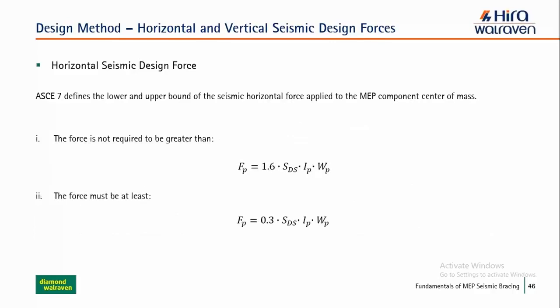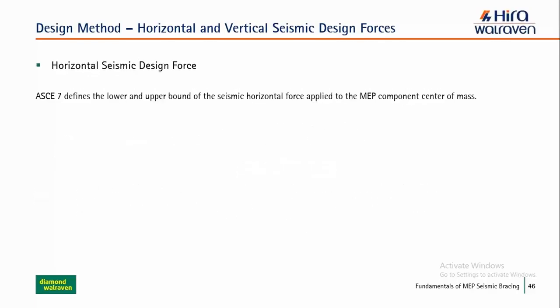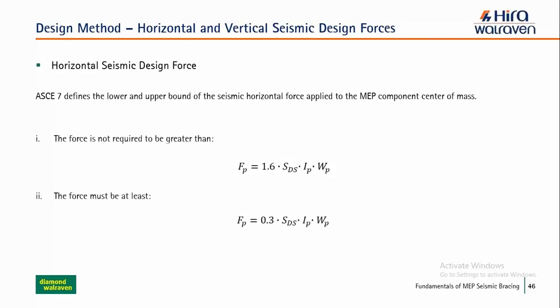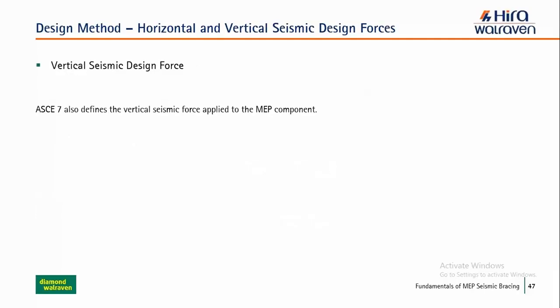Now we have upper and lower limits to counter check our values. This force is not to be greater than 1.6 times this equation, and this force must be at least 0.3 times this equation, the second one. If our Fp value comes out lesser than the force 0.3 SDS Ip Wp, in that case we need to consider the force coming from this equation. That is the reason the force must be at least the value given by this equation.